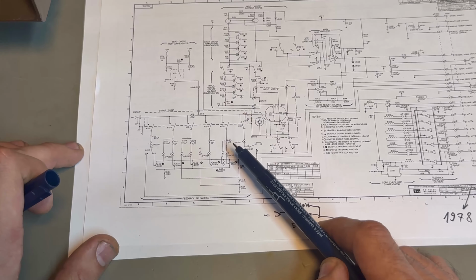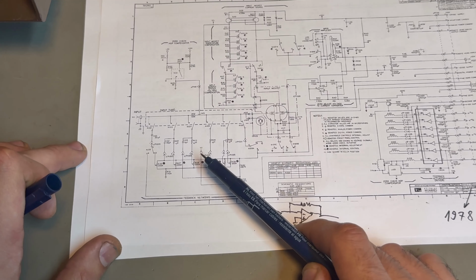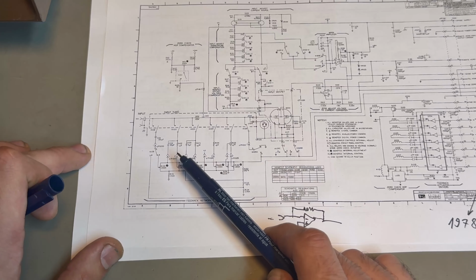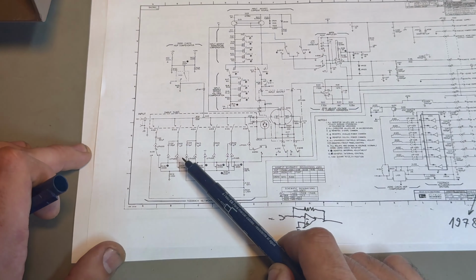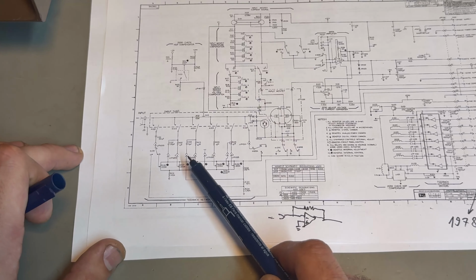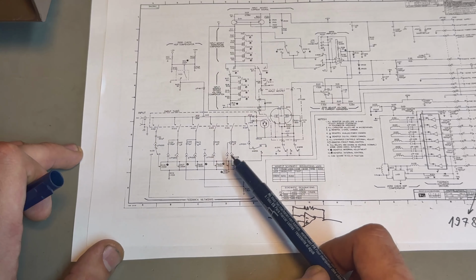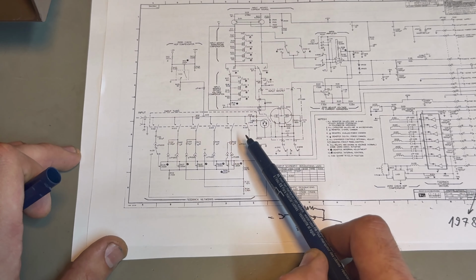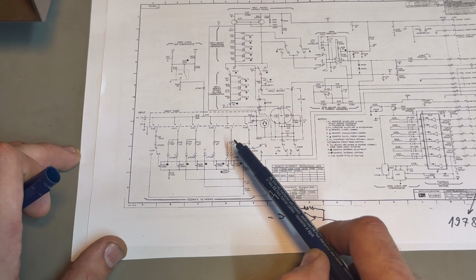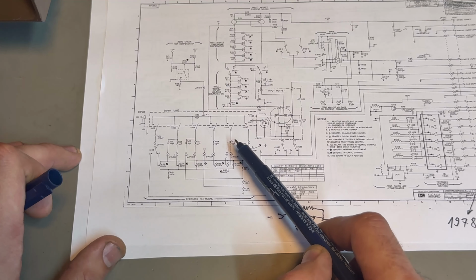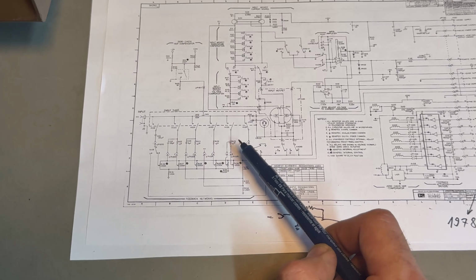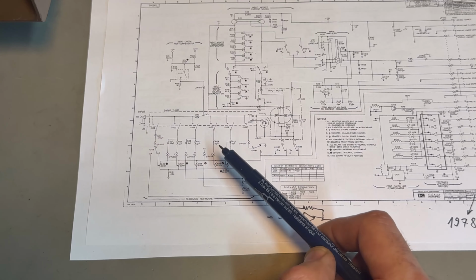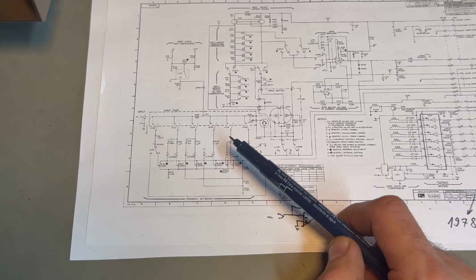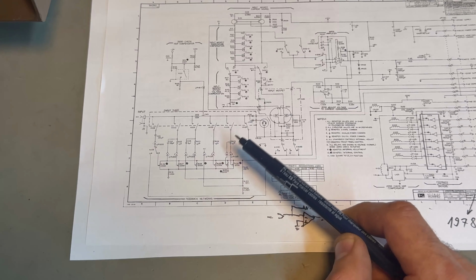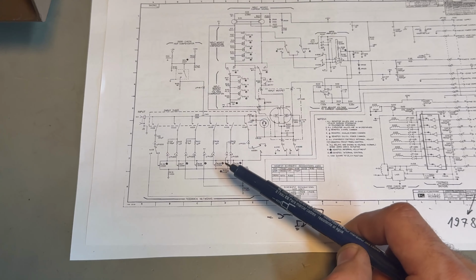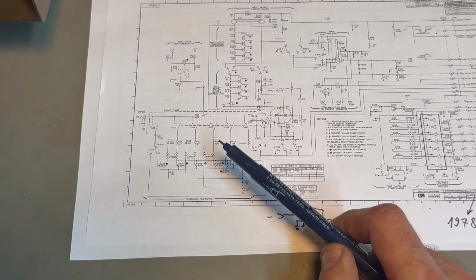So we have a tera ohm, 100 gig, 10 gig, and I think this is 10 to the 8th, 100 megs. All of them have some capacitance in parallel, with the exception of the two biggest ones. And you'll see that the biggest one even has a partially driven shield. So there's a shield that will collect the leakage current forming across the resistor. Usually high value resistors are encased in glass, but even glass has some leakage current, so they're usually wrapped in a shield, and that shield is actively driven to some potential to cancel out the leakage currents.